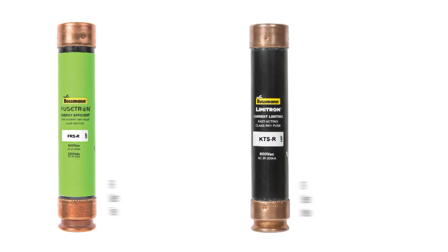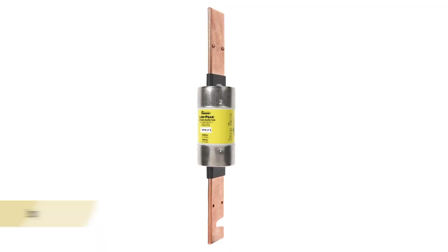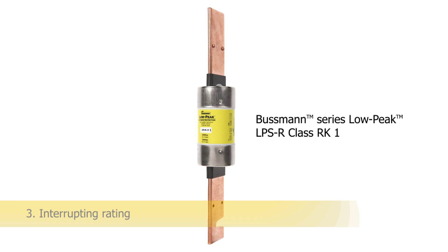As a rule, the fuse amp rating should be selected at no closer than 125% of the continuous motor load current. There are exceptions, such as when the fuse switch combination is approved for continuous operation at 100% of its rating. The third, and arguably the most critical, if not most misunderstood rating, is the interrupting rating.